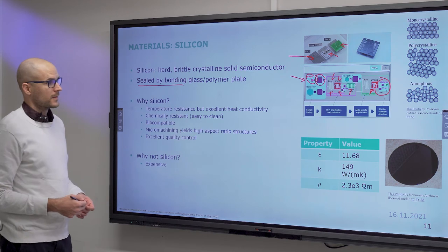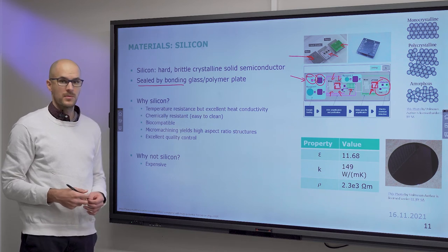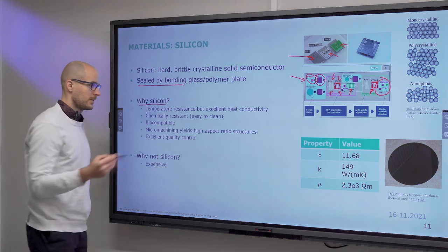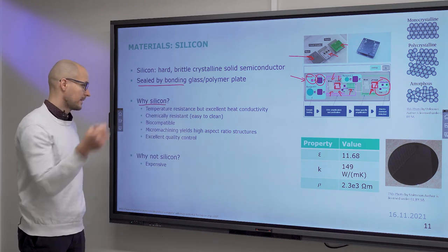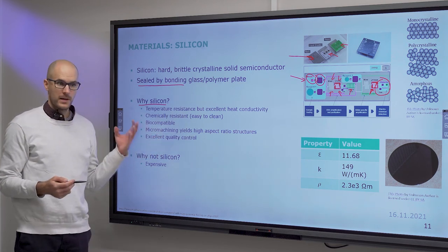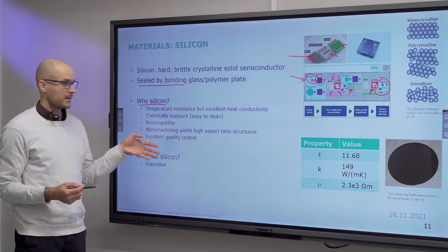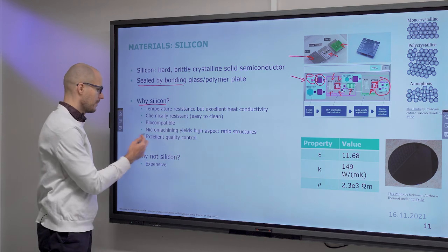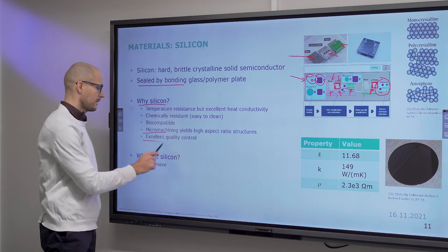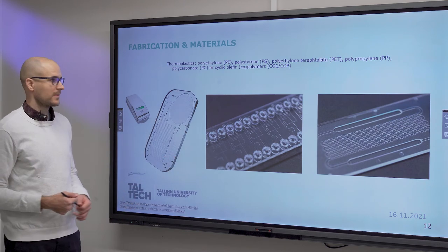Why would you choose silicon? The reasons are similar to glass, except that silicon is not transparent. But it is highly resistant to chemicals and temperature, has good heat conductivity, is biocompatible, you can make high aspect ratio structures from it, and quality control is excellent. The only problems are that it is expensive and not optically transparent.